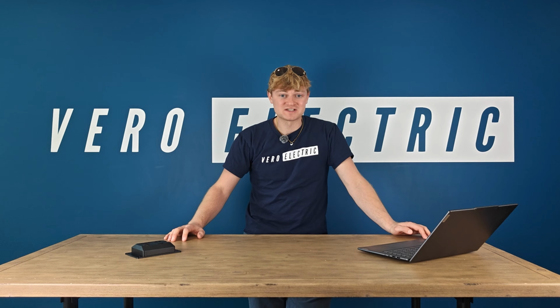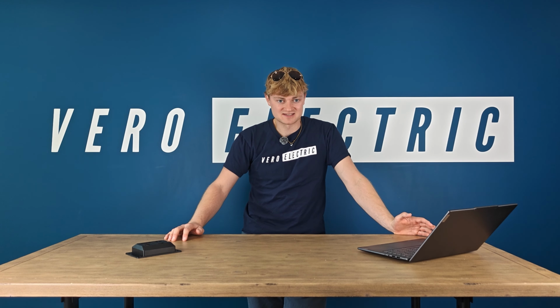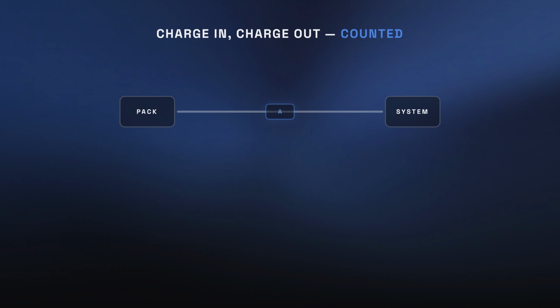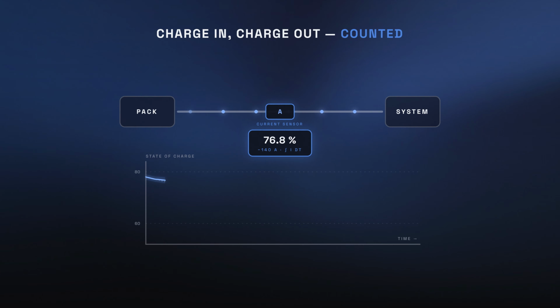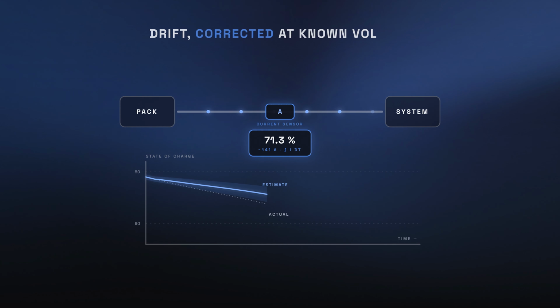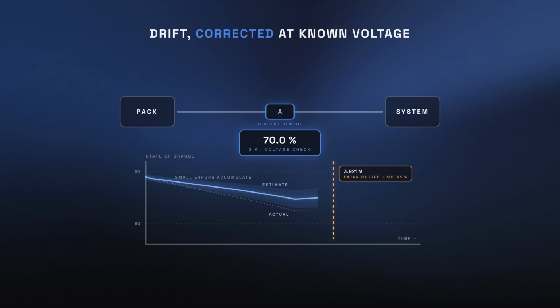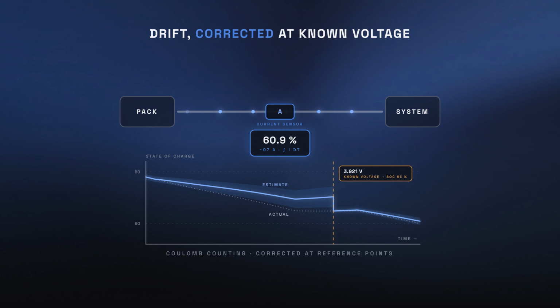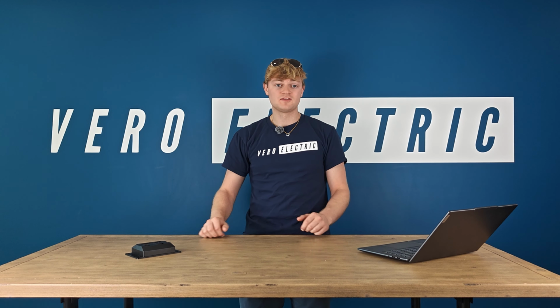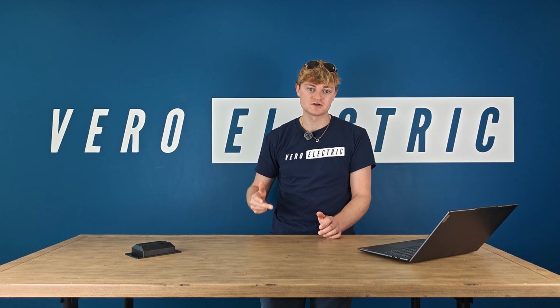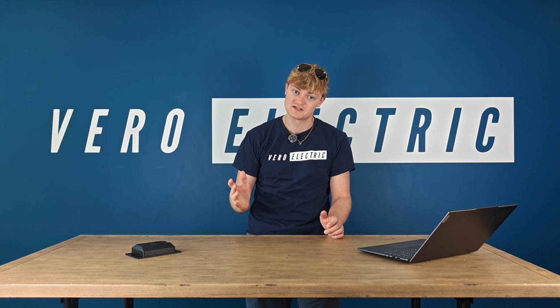The BMS also estimates state of charge, like we discussed last episode. The main tool is Coulomb counting, integrating current over time to track how much charge has entered or left the battery. Because small sensor errors accumulate, the estimate is periodically corrected using known voltage conditions or other reference points. From the same data, the BMS calculates how much charge and discharge current the pack can safely accept right now. Those limits can change continuously with cell voltage, temperature, state of charge, and pack health, or state of health.